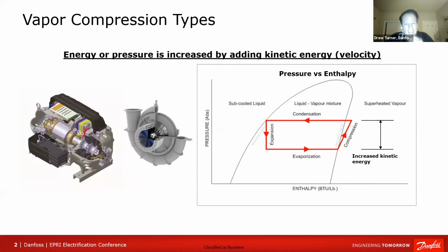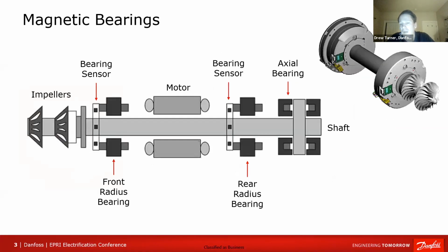But it started with the invention from a service tech in Australia roughly 25 years ago of a compression technology that was solving an issue with existing compressors, dynamic compression technologies that were in the field. And when you talk about dynamic compression, that's as opposed to positive displacement compression, which is a majority of the other technologies that are out there. But under dynamic compression, you have centrifugal compression and mainly other is axial. But with that technology, it's very different from positive displacement in that you're throwing the refrigerant instead of squeezing it. And with the throwing of the refrigerant, that's increasing the kinetic energy as opposed to increasing the potential.